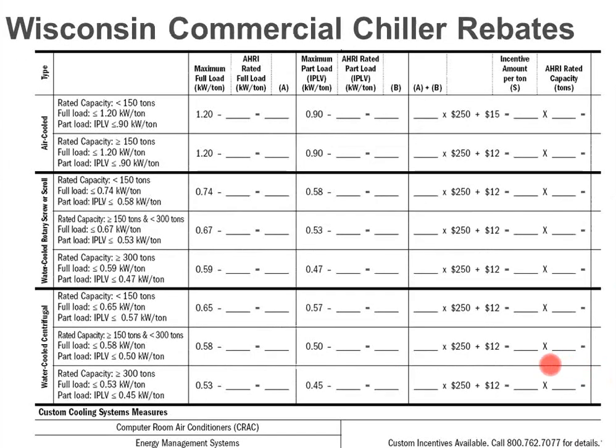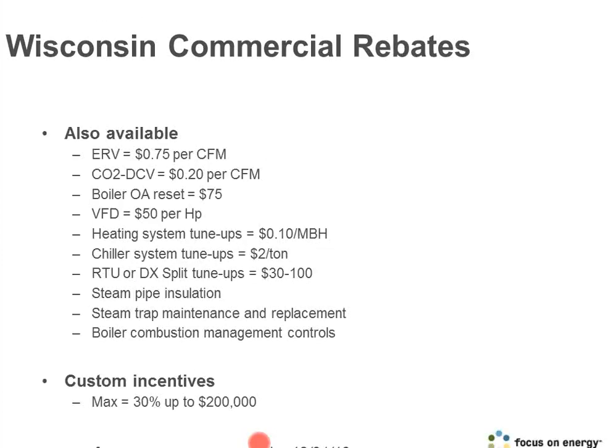There are chiller rebates in Wisconsin as well. There's a formula that you would have to fill out, but you do have to meet both a full load efficiency and a part load IPLV in order to get these rebates. There's a section for air-cooled, above and below 150 tons, and then there's water-cooled depending on whether you have a centrifugal or any other type of compressor. So scroll or screw would fall into that other category. But you got to meet the full load and the part load and then multiply everything out to figure out what your rebate's going to be. They do have some other specialty rebates for computer room units, building automation systems, and process type stuff. It's kind of on a custom basis, if you will.